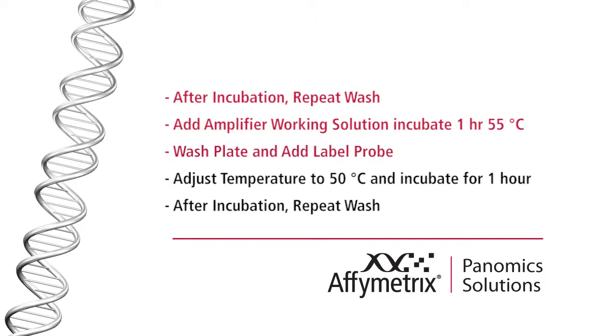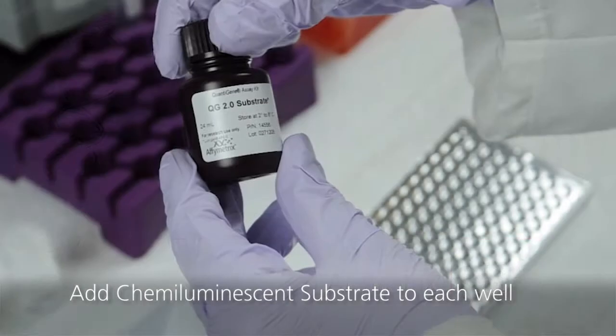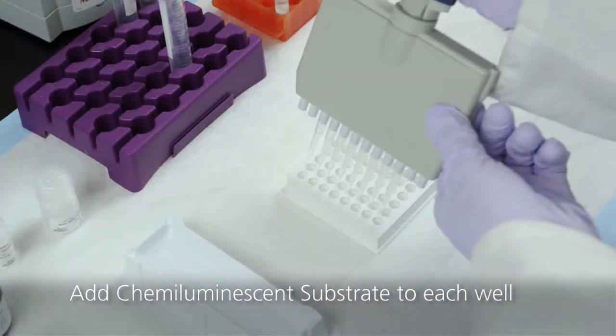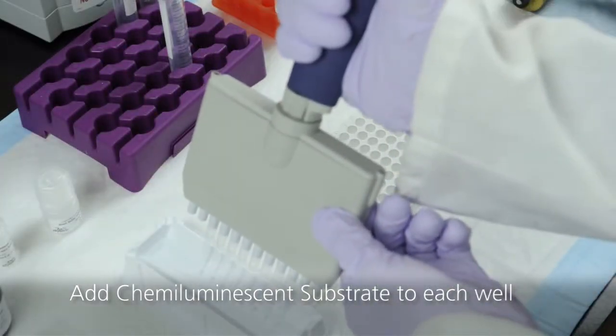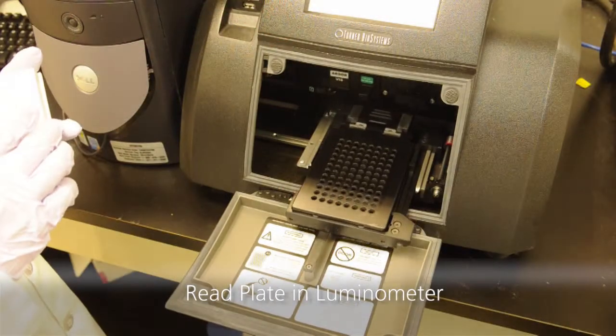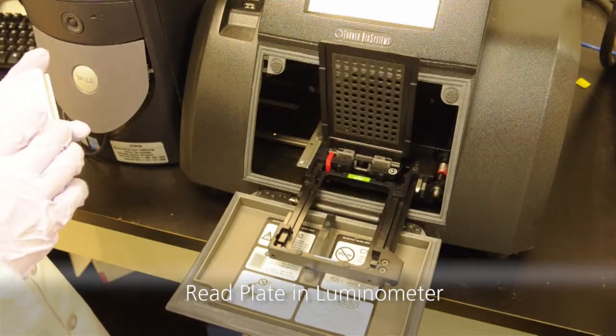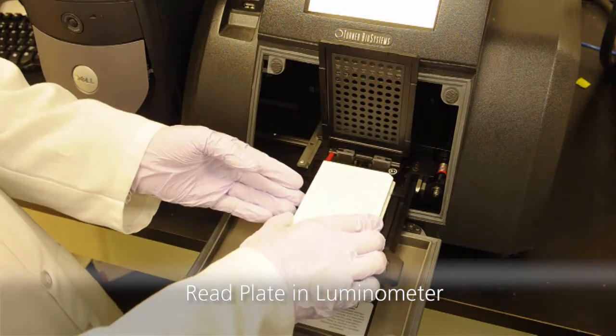After incubation, wash as previously described and add label probe working solution to each well. Adjust the temperature of the incubator to 50 degrees and incubate for 1 hour. After incubation, repeat the wash steps as previously described. Add the chemiluminescent substrate to each well and incubate for 5 minutes. Place the plate into the luminometer and set the integration to 0.2 seconds. For best results, read the plate within 15 minutes.